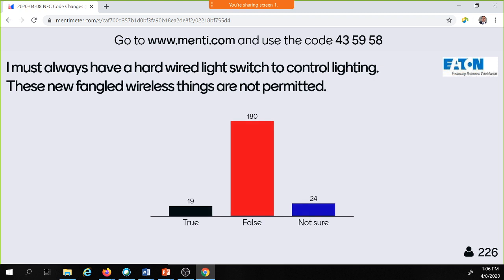I must always have a hardwired light switch to control lighting. These newfangled wireless things are not permitted. That would be false, because we're going to talk about that today - those newfangled wireless things are permitted now in the 2020 version of the code to use, but not in the older versions of the code. In the older versions, you have to have this light switch, you've got to pull that wire down to the light switch because of the way the language was written, but not today.